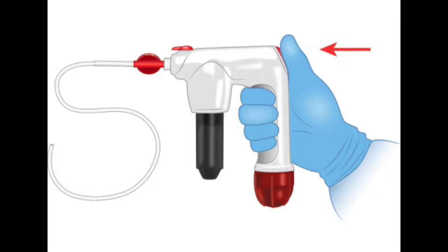The pressurized CO2 violently ejects the powder out of the tip. Typically, each full successful pull of the trigger delivers about 2 grams of the compound directly onto the bleeding site. 2 grams. And the endoscopist will use multiple cartridges, right? Sometimes up to 3, layering the powder on, pulling the trigger again and again until they visually confirm that the bleeding has stopped and the mechanical matrix has fully formed. Yes, exactly. But, okay, we have to address the what-if scenario.